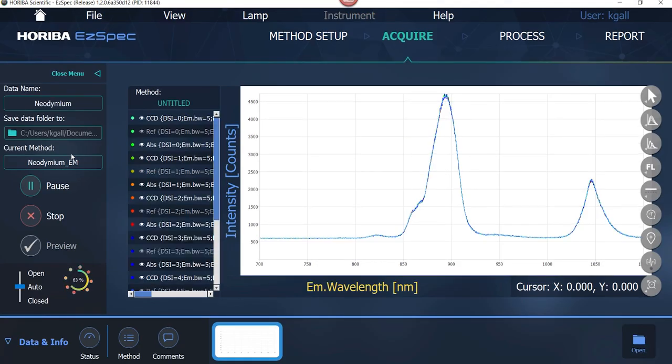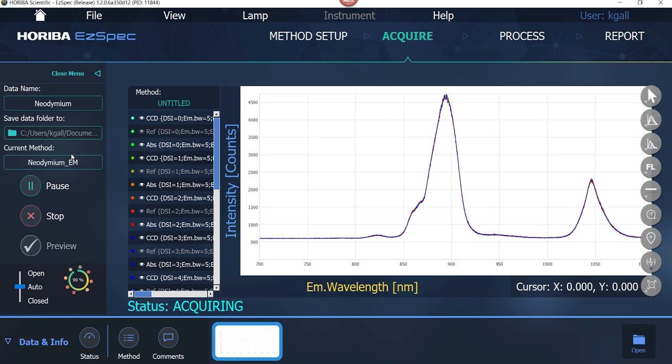So it's the speed combined with the fact that it's doing absorbance and transmission that really make it quite unique. In particular, it's not just that it can do absorbance or fluorescence, but we use the absorbance to correct the fluorescence that we get.